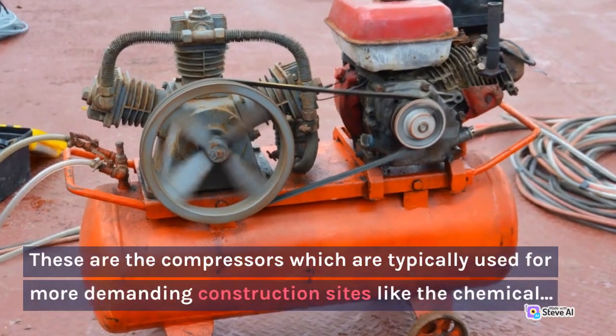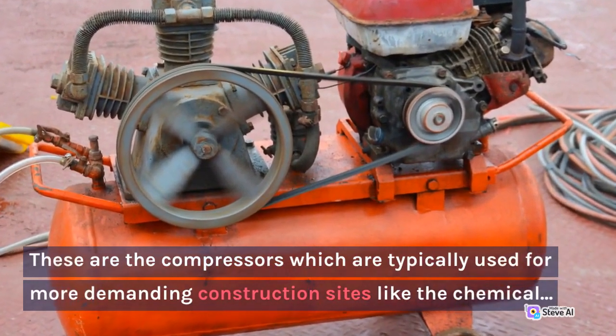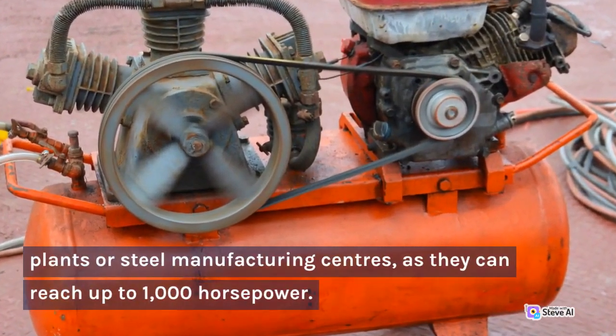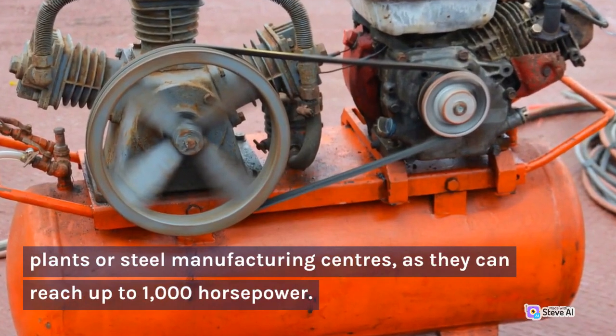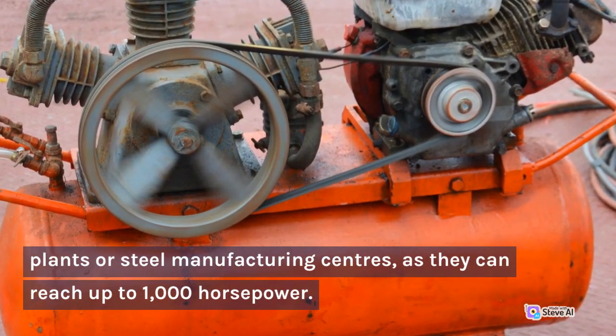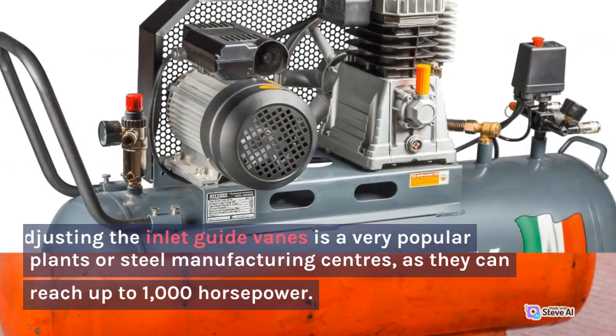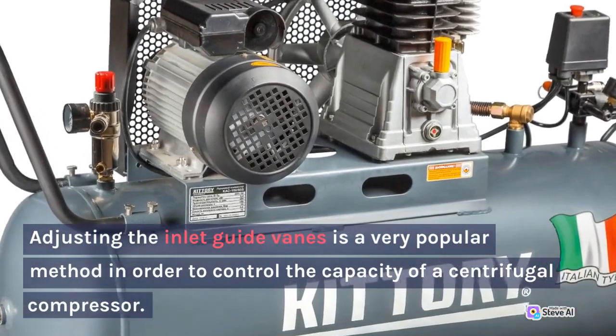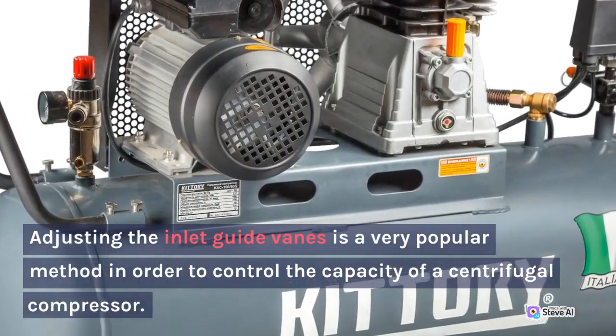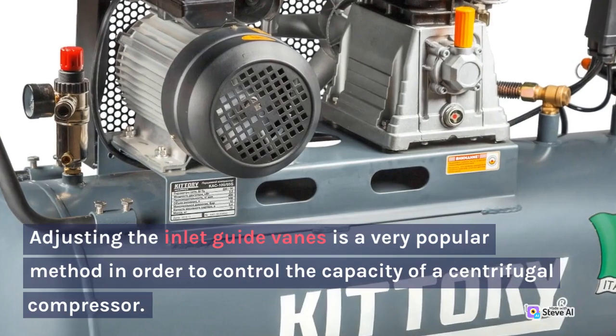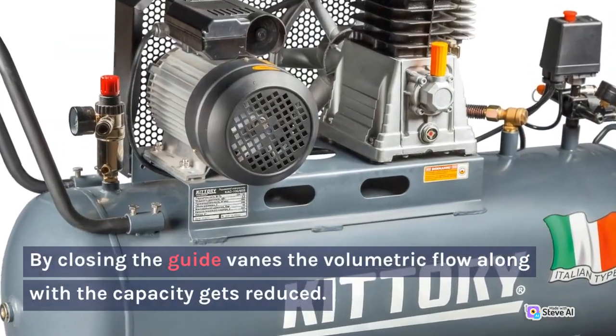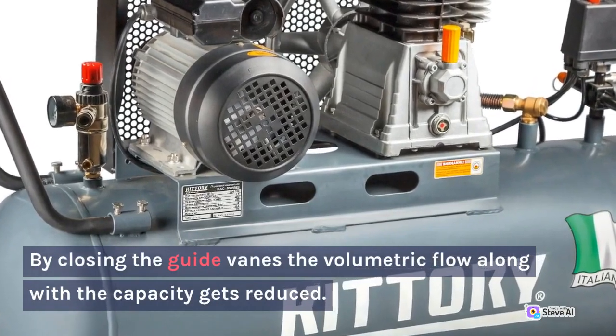These compressors are typically used for more demanding sites like chemical plants or steel manufacturing centers, as they can reach up to 1,000 horsepower. Adjusting the inlet guide vanes is a very popular method in order to control the capacity of a centrifugal compressor. By closing the guide vanes, the volumetric flow along with the capacity gets reduced.